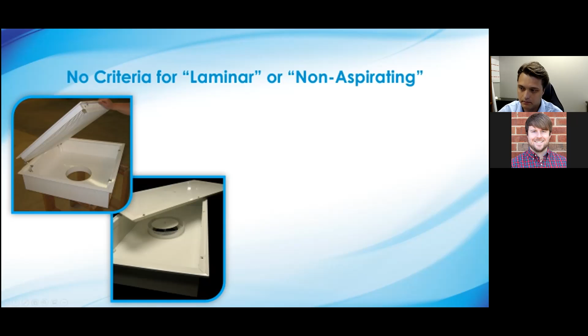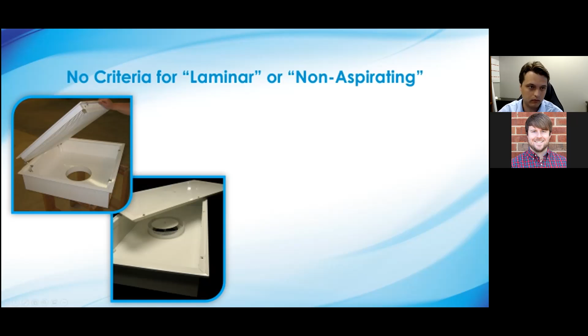There's no baffling within there, no series of chambers. And here's another kind of excuse of a laminar flow diffuser that's just a little perforated ring around the inlet and then just a faceplate on it. This is undoubtedly going to have less uniform characteristics of that airflow coming out than something with an actual engineered baffle within it. Another side note is that some of these units could even have cracks and crevices in them that are big enough to literally put a piece of paper through.